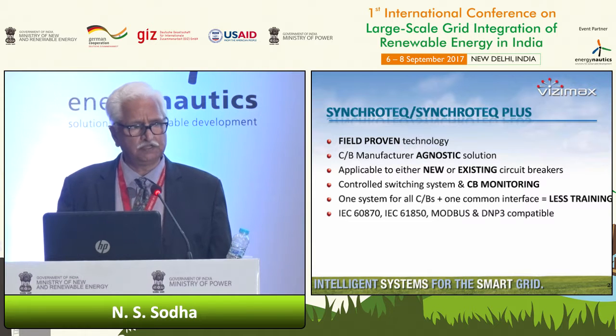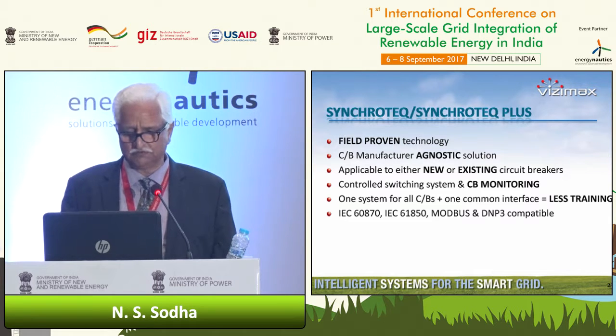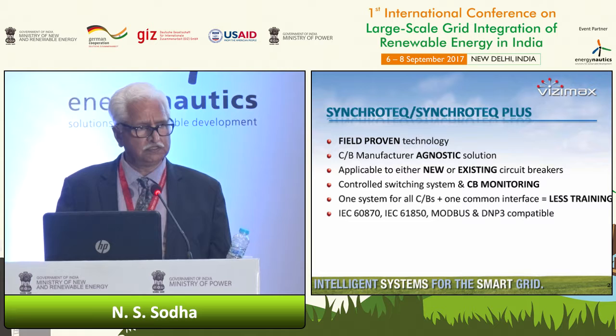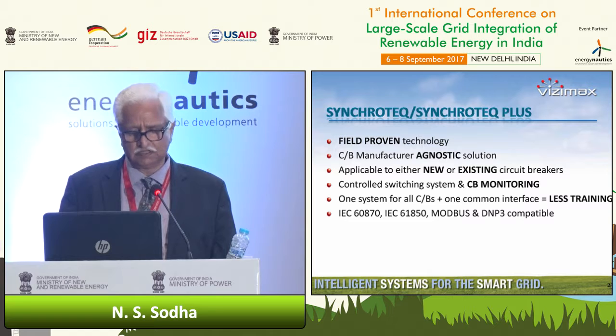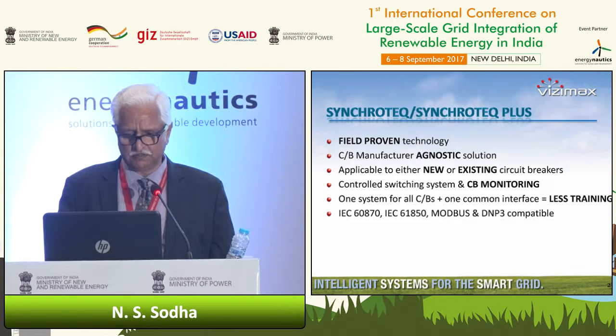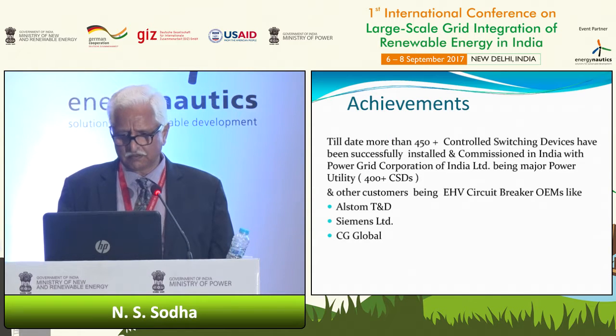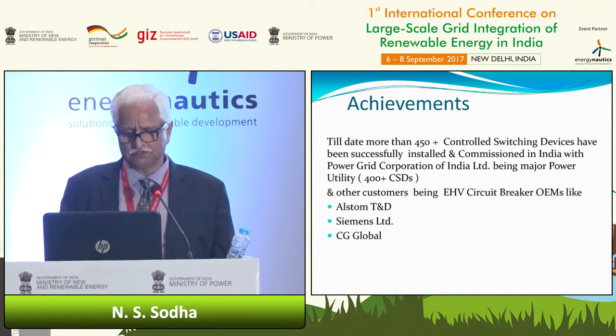Power Grid has also done retrofitting in the last 3 years, and close to around 450 circuit breakers have been retrofitted. And now all the new circuit breakers in 765 kV, particularly for transformer switching and shunt reactor switchings, are coming with the CSD retrofitted. And it's hardly any training required. And the achievements, as I mentioned, 450 control switching devices have been installed, and other customers also, like Alstom and Siemens and Cromptons, they are using the CSD of this make.